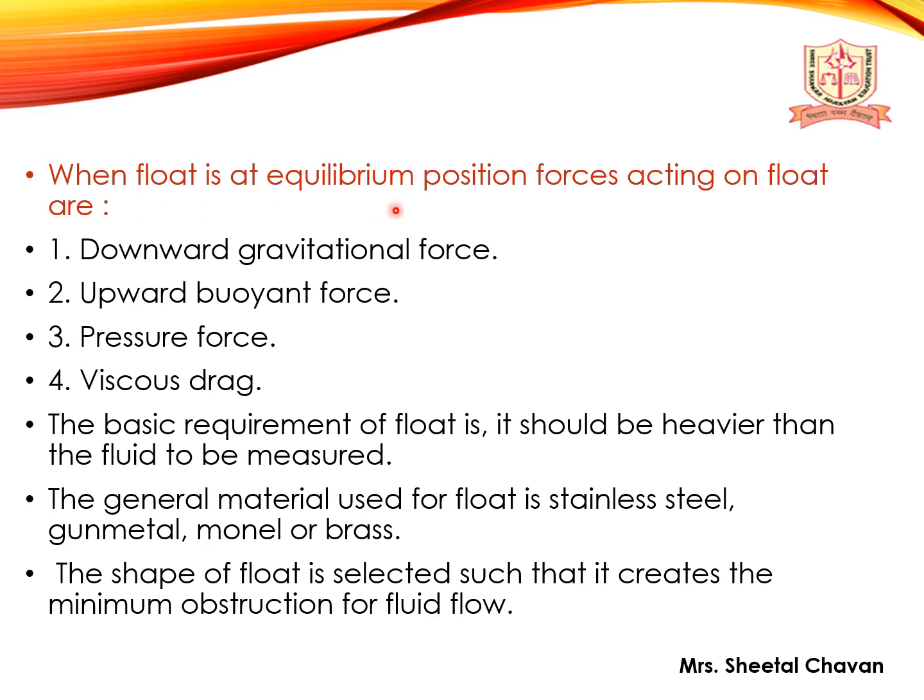When the float is at the equilibrium position, the forces acting on the float are the downward gravitational force, the upward buoyant force, pressure force and viscous drag. The basic requirement of the float is that it should be heavier than the fluid to be measured. The general material used for the float is stainless steel, gunmetal, monel or brass. The shape of the float is selected such that it creates the minimum obstruction for the fluid flow.